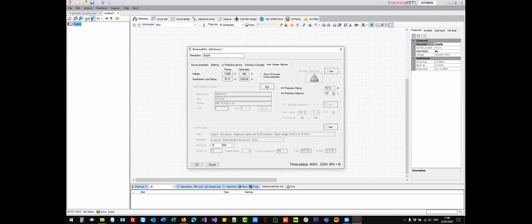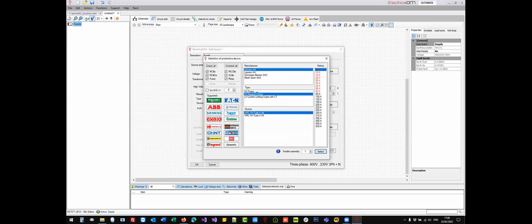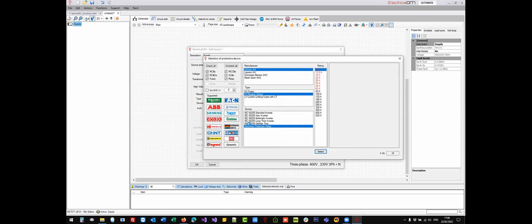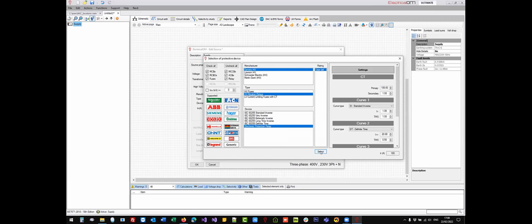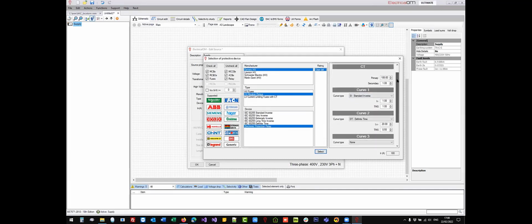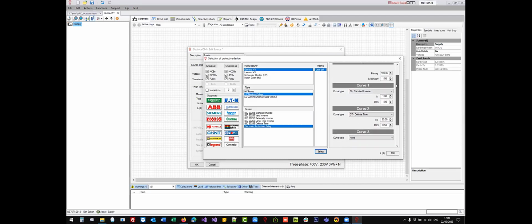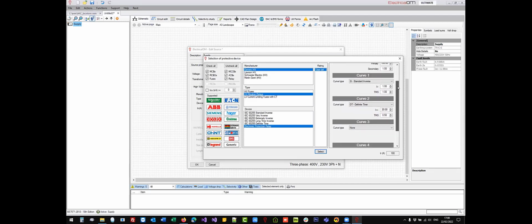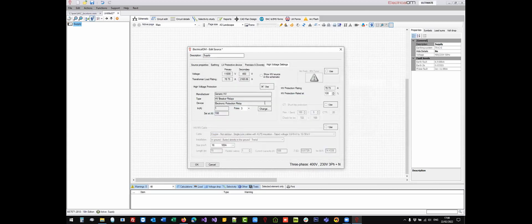So here I will choose to use a high voltage protective device, where I will select a relay with electronic protection. Okay, so this is a new item that we have included in the latest version, where you can define the relay settings and also the CT parameters, and we support up to 4 curves. Selecting that now, we can choose to use the arc flash assessment here for the medium voltage panel.